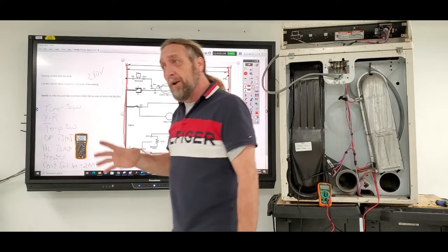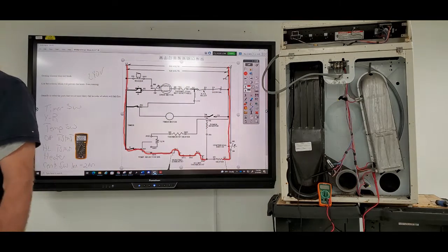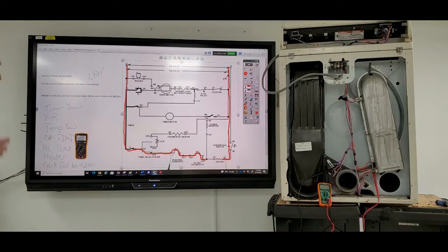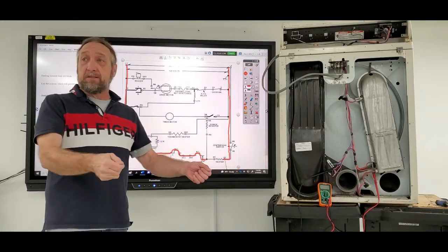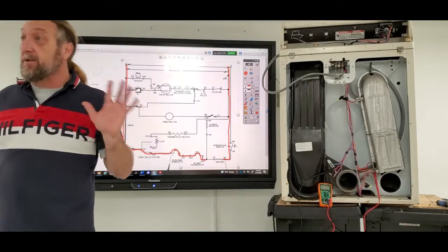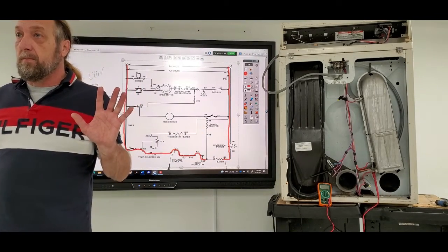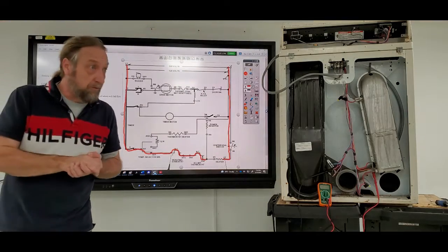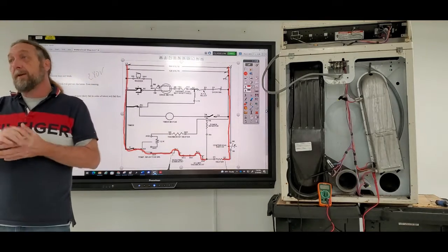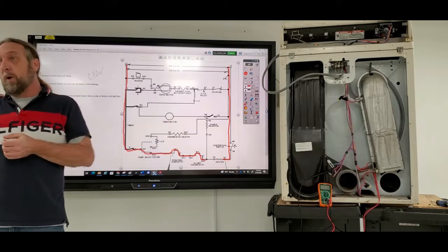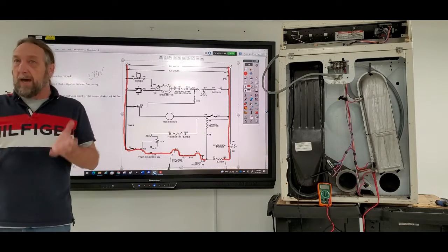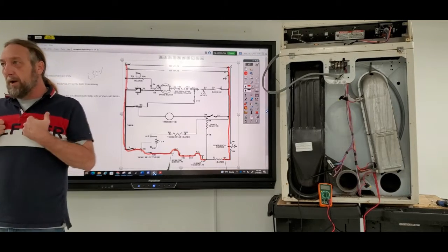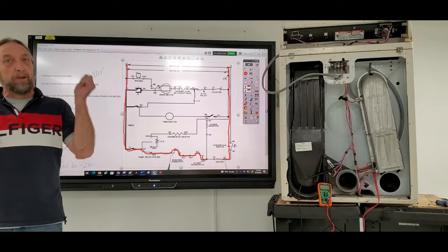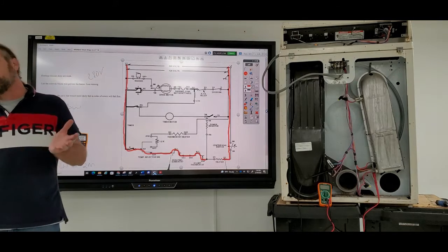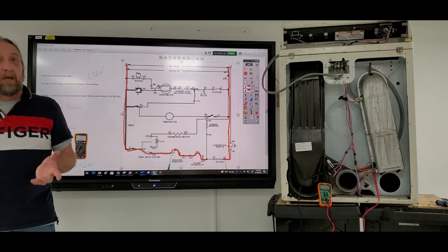Now, one important thing I didn't mention at the beginning: when doing a voltage test, if you can unplug the machine, set your meter, and get your hands out, it's the safest way. If you wear gloves and are secure in your testing, yes, you can do what I did while it's live, but it's very dangerous, so you have to be careful. I recommend gloves, unplug the machine, move your meter, then plug it back in to start it. Yeah, it takes a little longer, but it's the safest thing.